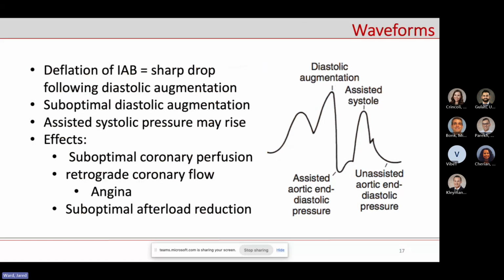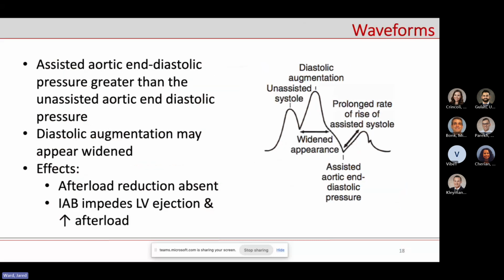And then there's obviously too late of deflation, where you'll get the widened appearance of the balloon. It increases your afterload, just because the ventricle is trying to contract while the balloon is still inflated. So you're just pumping against a harder pressure, which is basically negating everything that the balloon pump theoretically should do. So just make sure before you walk into your board exam, you look over the waveforms, because that's what's most commonly going to be tested.